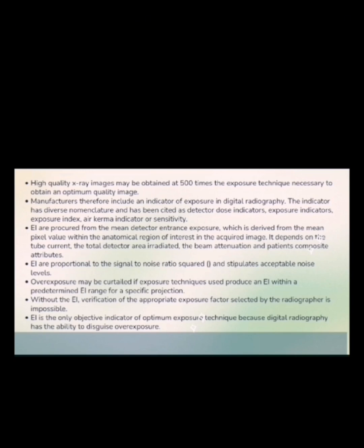That's why exposure indicators are procured from the mean detector entrance exposure, which is derived from the mean pixel value within the anatomical region of interest in the acquired image. It also depends on the tube current, the total detector area irradiated, the beam attenuation, and the patient's composite attributes.